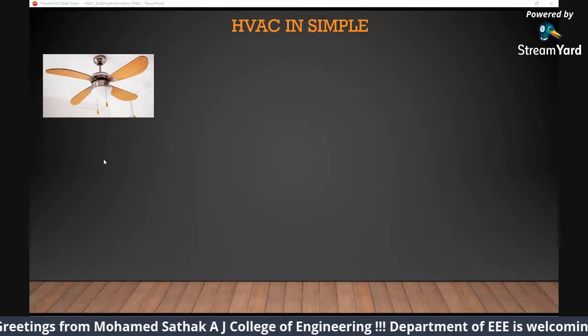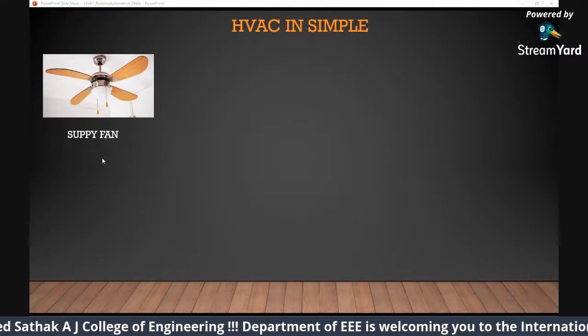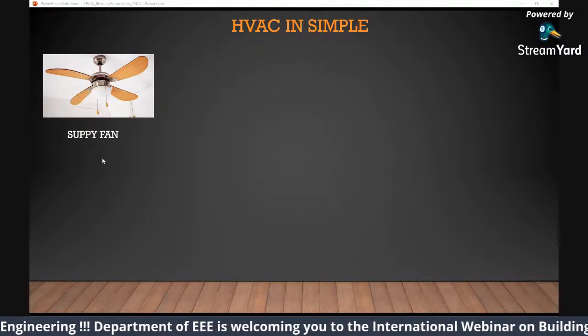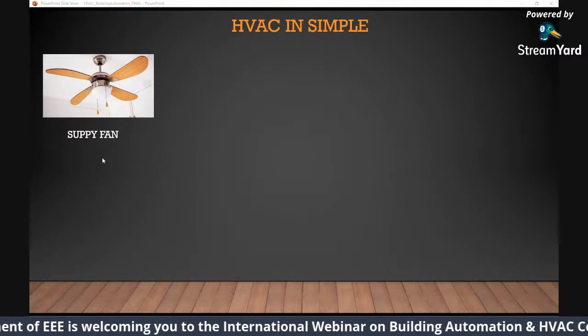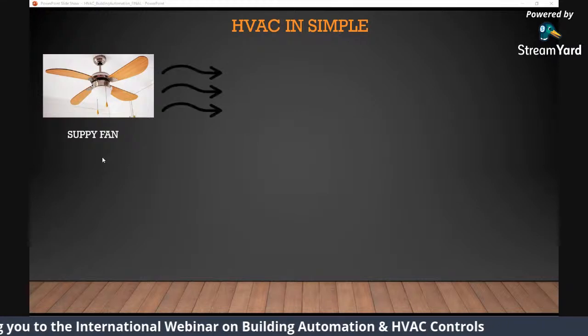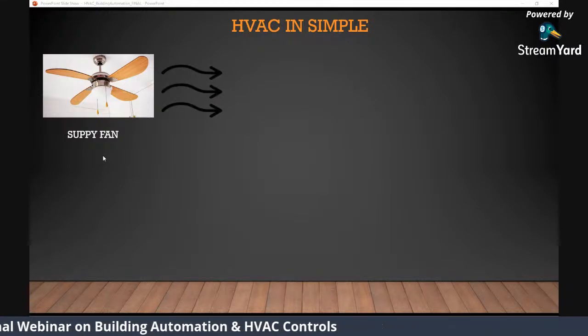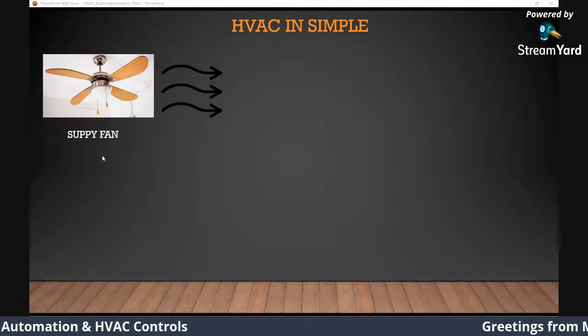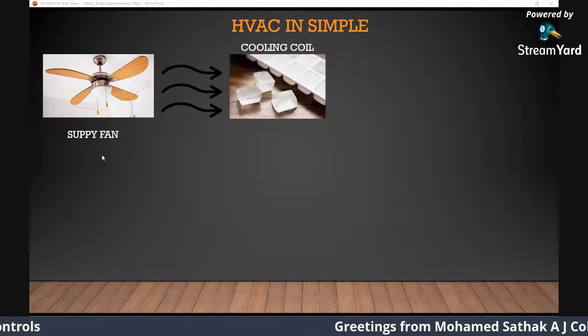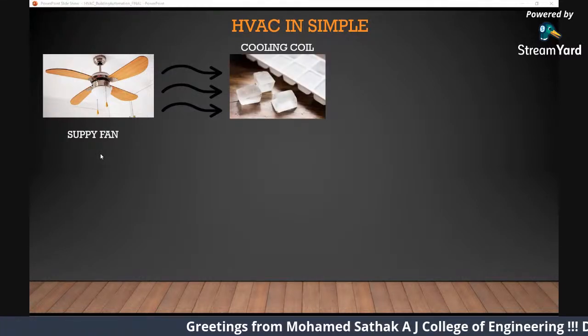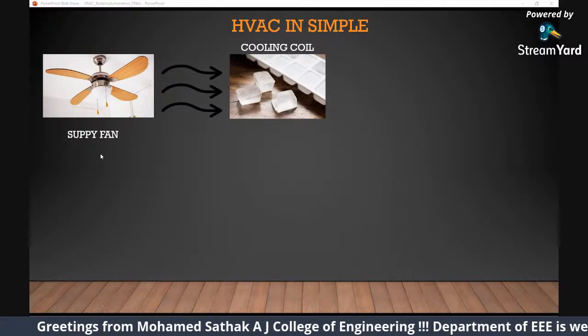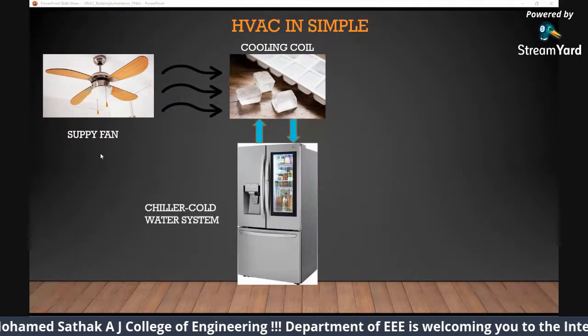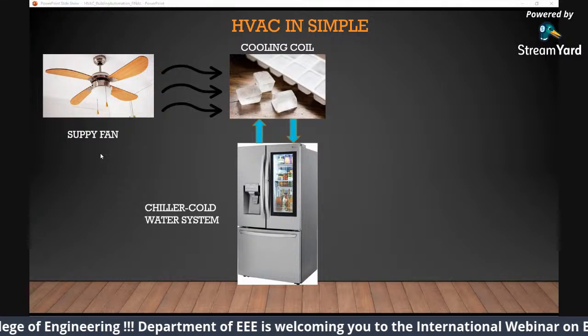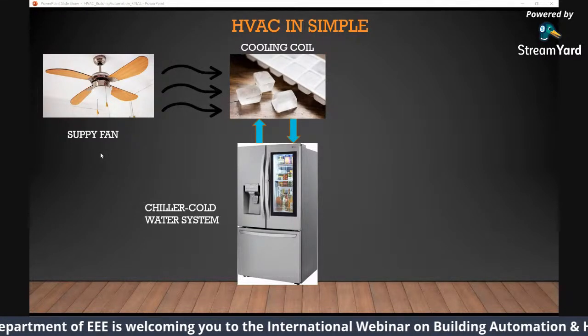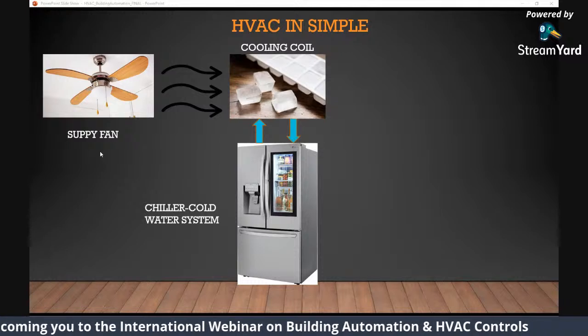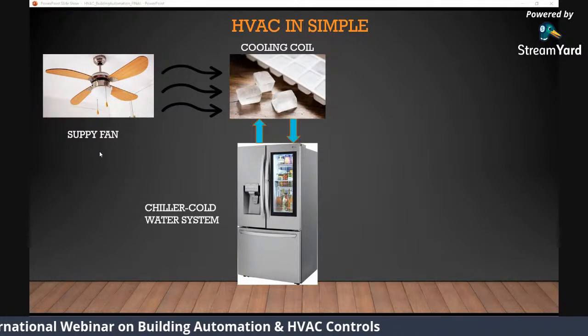So to put it in an old concept, we have the AHU, which is nothing but a unit that supplies airflow to your building or your closed space. So consider it as a supply fan or a ceiling fan. Now, what does it do? It supplies airflow. Now, let's say it's too hot outside. What do you need? You need cold air. So where do you get it? You need a cooling coil. When your airflow passes through your cooling coil, you get cold air. And where do you get the cooling coil's chilled water from? You get it from your chilled water system. And it's classified into air cooled chiller and water cooled chiller based upon the type of cooling of your refrigerant inside the condenser, right? So I hope you're clear till this.